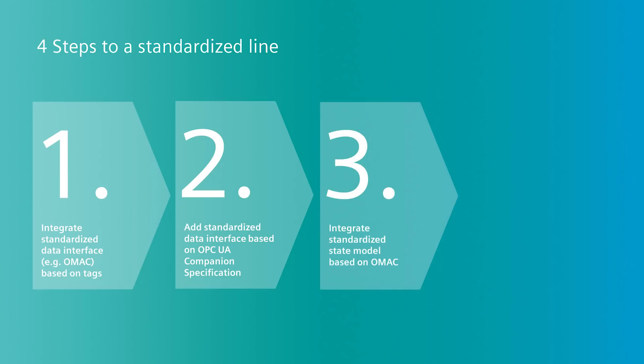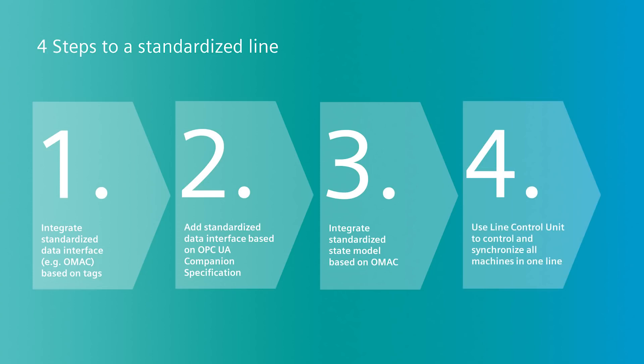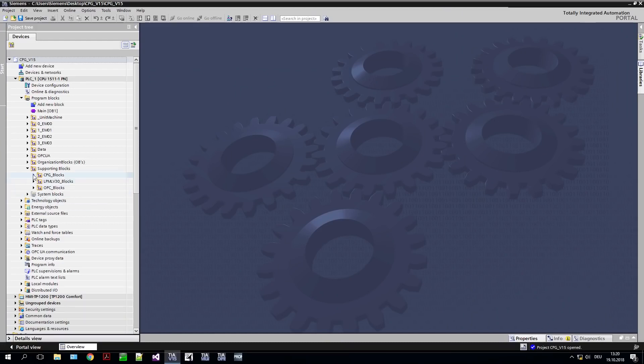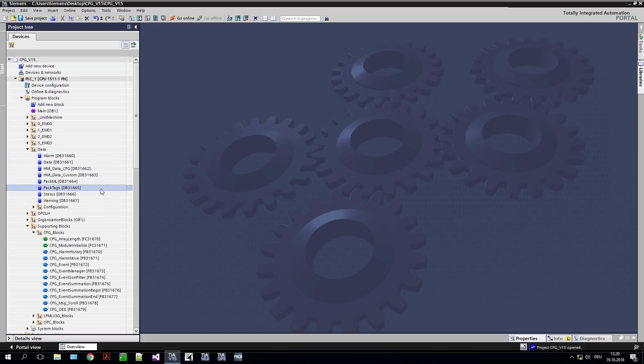Once the data interface is standardized and implemented, I'll show you how the behavior of a machine can be standardized using standardized status models in the next step. These standardized data interfaces are created and maintained by industry associations such as the OMAC Foundation. Industry associations like this make specifications available which define how a data interface must be constructed, such as for the very well-known OMAC PackML standard. A TIA Portal library containing all the function and data modules required for integrating this interface into a SIMATIC S7-1500 is available to you free of charge.